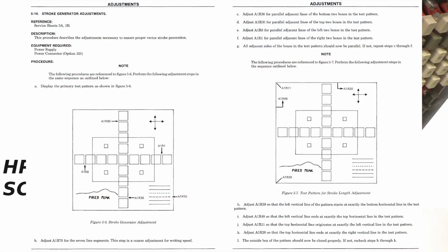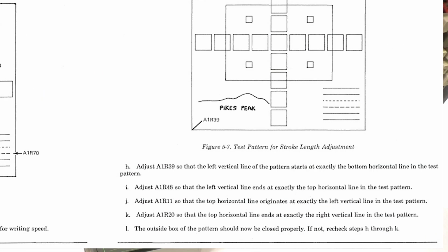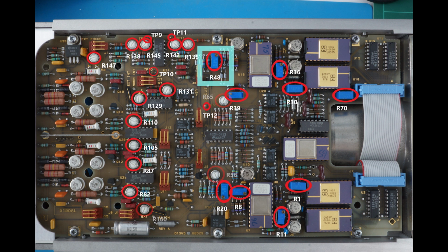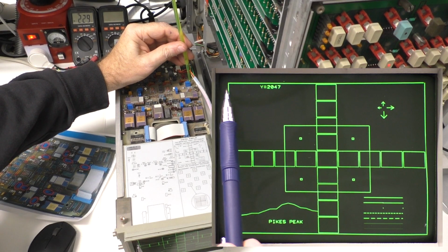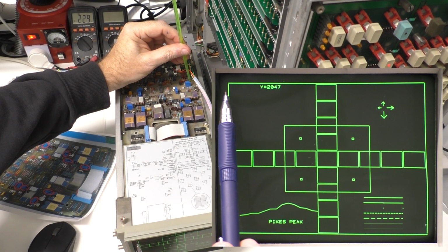Moving on to stroke generator. 5-14-H through L. These ensure the horizontal and vertical lines meet at the extremities. Locate R48 on the A1 board. This adjusts the left vertical line extremity of the test pattern. Adjust R48 so that the left vertical line meets the end of the top horizontal line.